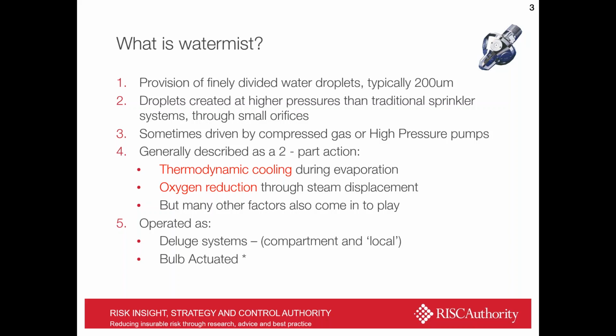In order to achieve this very fine subdivision of particles, generally these systems might operate at much higher pressures than other traditional water systems, and for this we might use compressed gas or high pressure pumps. The mode of operation is generally described as a two-part thermodynamic cooling of gases during the evaporation process of water into steam, and oxygen reduction as this steam displaces oxygen from the compartment. But many other factors will also come into play, and I'll show you that in probably more detail than is healthy during the course of this talk.